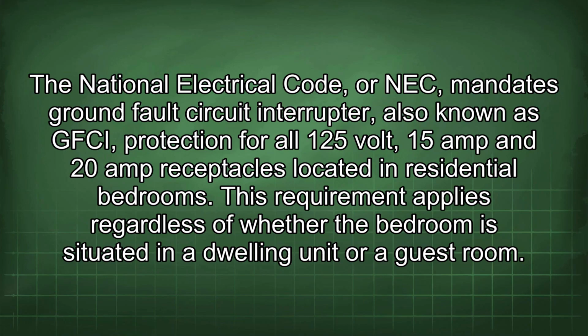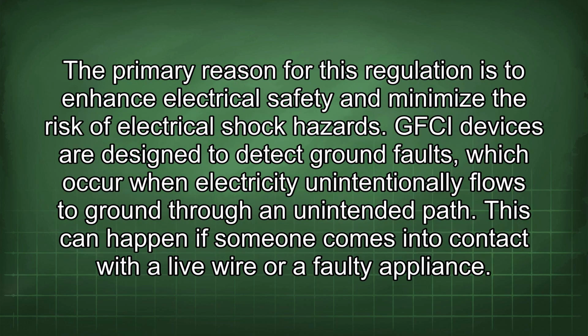The National Electrical Code, or NEC, mandates ground fault circuit interrupter, also known as GFCI, protection for all 125 volt, 15 amp and 20 amp receptacles located in residential bedrooms. This requirement applies regardless of whether the bedroom is situated in a dwelling unit or a guest room. The primary reason for this regulation is to enhance electrical safety and minimize the risk of electrical shock hazards.